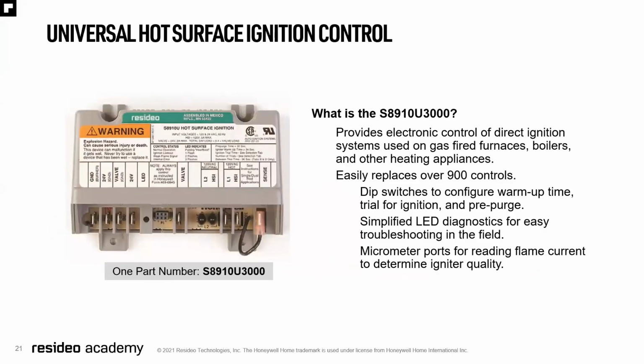The universal hot surface ignition, the S8910U 3000. We call it the sister of the S8610U. It's a fantastic control for one-stop shop, replacing almost every hot surface ignition control. Replace over 900 controls. It has a dip switch configuration to configure your warm-up time, your trial for ignition, and your pre-purge. Has little LED diagnostics for troubleshooting. And again, it has ports for reading flame current to determine igniter quality.